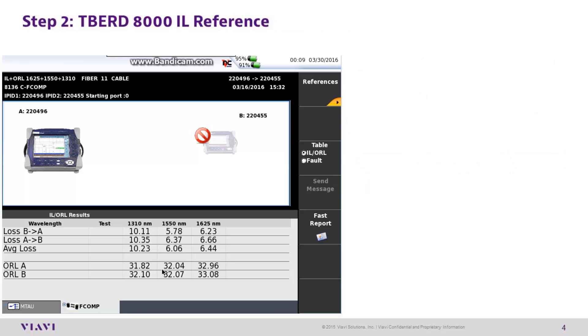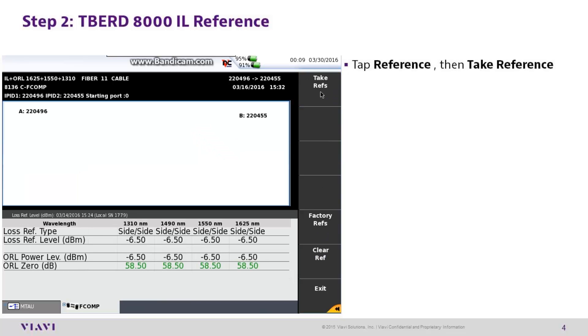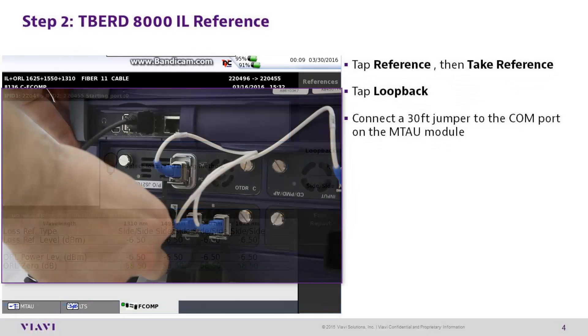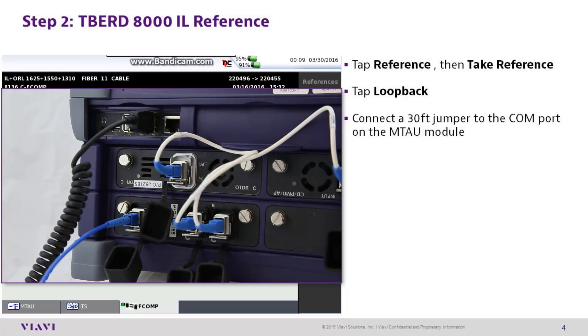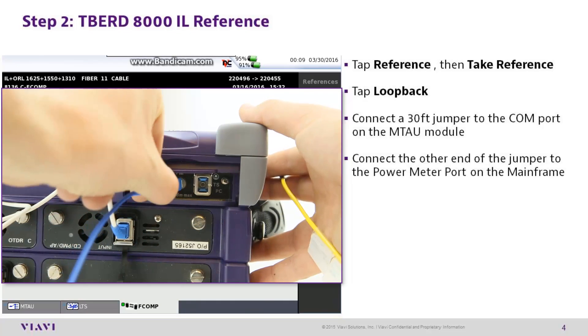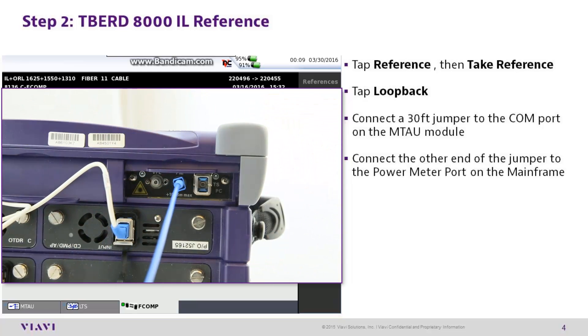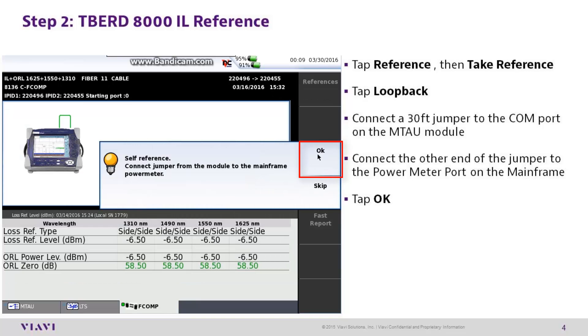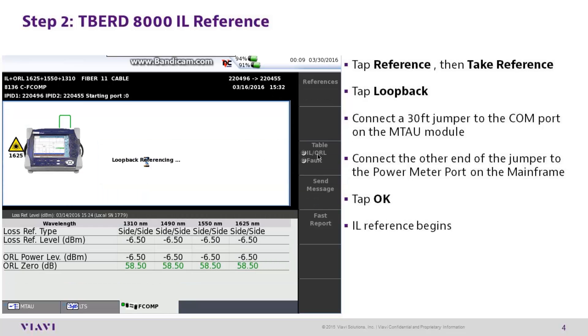T-Bird 8000 step 2: insertion loss reference. From the fComp tab, tap reference, then take reference. When prompted, tap loop back. Connect a 30-foot jumper to the COM port on the MTAU module, then connect the other end of the jumper to the power meter port on the mainframe. Tap OK. The insertion loss reference will begin.